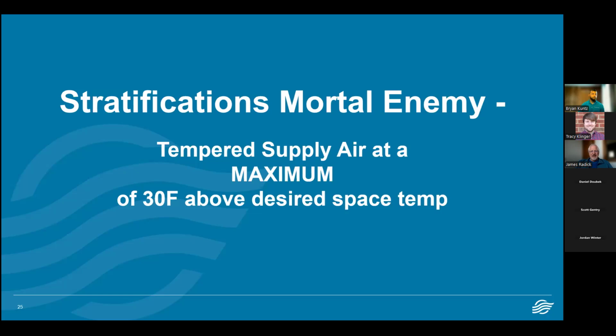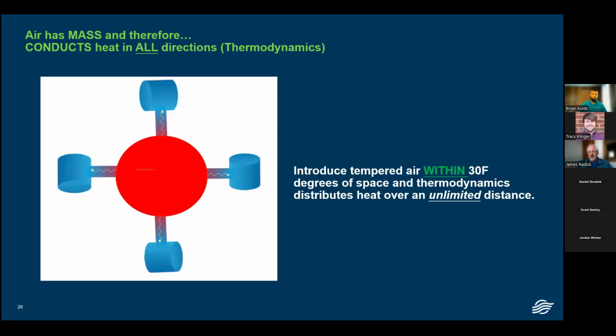Stratification's mortal enemy is low supply air temperature of about 30 degrees above the desired space temperature. And that's what the Weather-Rite products controls that we have do. We will strive to maintain positive pressure because it then gives us control over all of the air in the facility instead of cold air coming in and laying along the floor and pushing heated air to the ceiling. We maintain that slight positive. It makes everybody more comfortable around the space. It gives you even temperatures throughout the space.